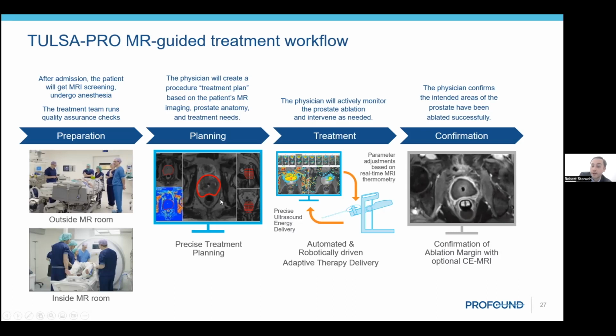Once the plan is designed, then the treatment is performed automatically under this real-time temperature imaging control, where the MRI is acquiring images that are then transferred to our software. The temperature is calculated and displayed. That temperature is also used to adjust the treatment parameters so that the treatment matches the physician's intended ablation volume. And then the physician is there to intervene and adjust the plan as needed as it proceeds.